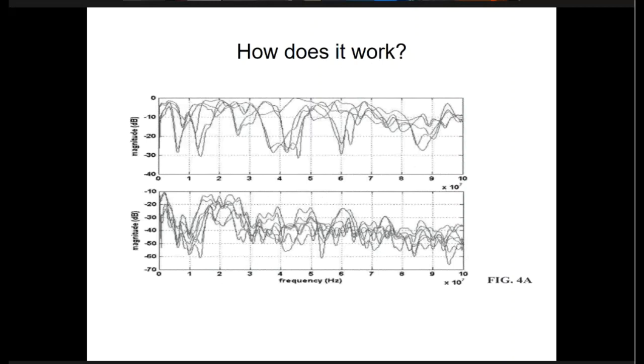And what it's doing is actually looking at the waveform presented on the voltage, so it's keeping track of the voltage. You'll notice the scale on here says 10 to the 7th power—so this is 10 megahertz to 100 megahertz being shown on this spectrum analysis graph of what frequencies it's seeing.